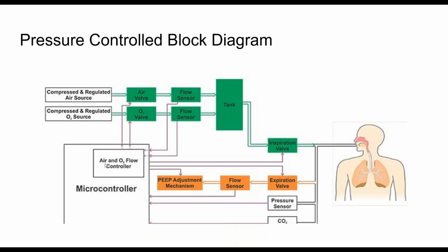Air and O2 need to be mixed at a certain ratio, depending on if you have an O2 source for your ventilator connected. Normally, we breathe 20.9% oxygen, give or take a little bit, depending on higher altitudes. Patients may need a little bit more of an oxygen-enriched environment, up to 100%. So this proportioning system is very important to get the right amount of gases, and the right amount of oxygen primarily, to the patient to absorb or respire into their cells.